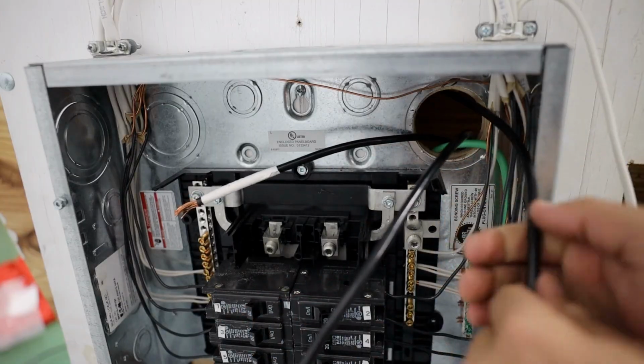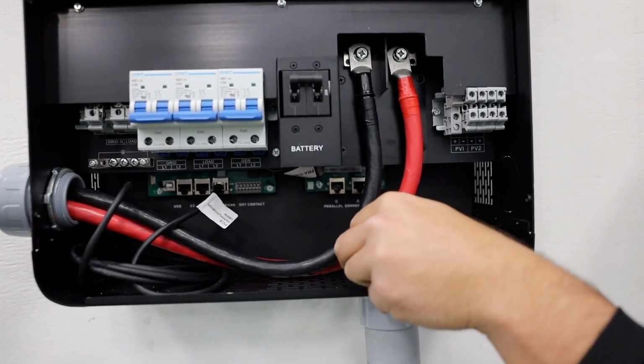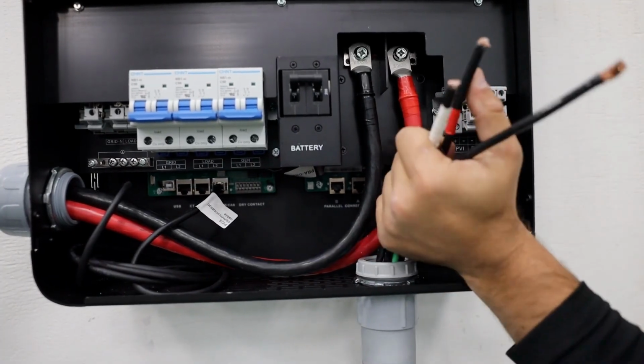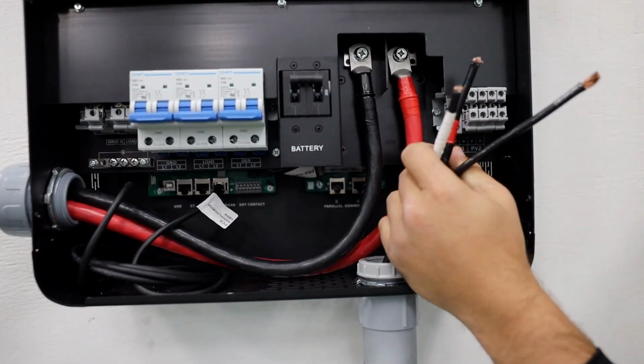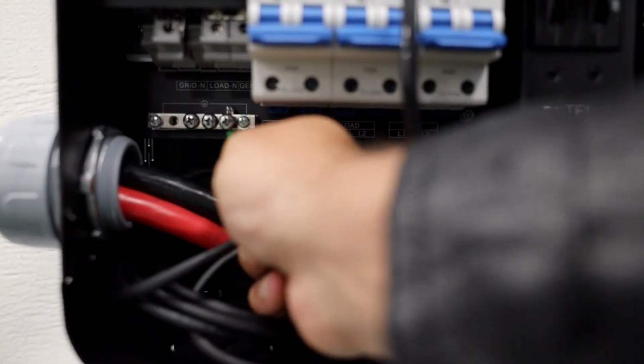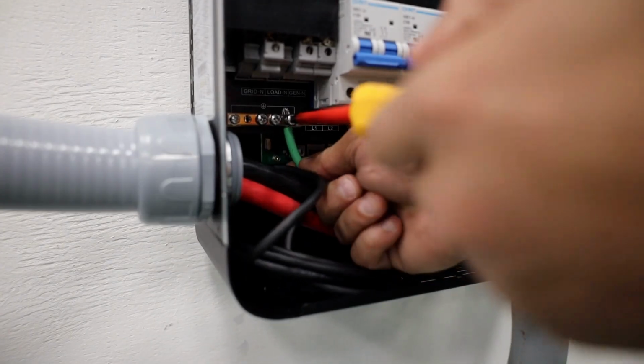For demonstration, we have attached the load panel to the back of the mock rollable wall. Before routing the cables, make sure to turn off all load breakers. Then proceed to route the neutral, ground and line cables from your load panel to your inverter.